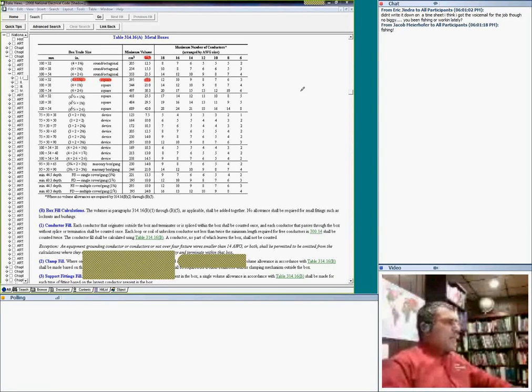Now if I'm using this box as a J box, and I decide, I'm in a commercial, so I use all number 12. I can bring number 8 conductors to this box as a J box. Okay, easy. I have my conduits coming in here, other conduits coming in here, and a third conduit coming over here, and I'm going to splice these conductors.